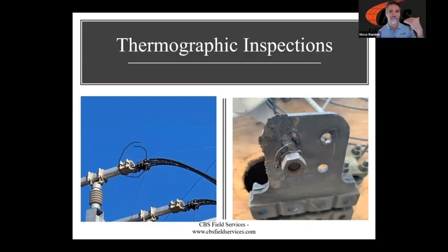Another one, this is the minimum barrier to entry if you want to have good substation maintenance and good substation practices, and that is get your thermographic surveys done. Once again, we had a thermographic problem show up on this paddle right here of this outdoor substation bus. Once it was taken offline and repaired, you can see the damage that was being done.